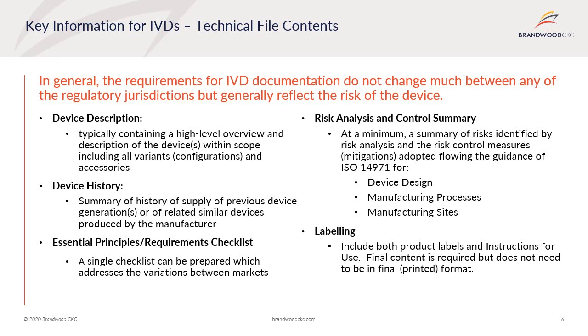So first, you would start out with a device description. Again, pretty self-explanatory. It's typically just a high-level overview description of the device, its scope, and any variants or configurations that might be included, as well as the accessories.